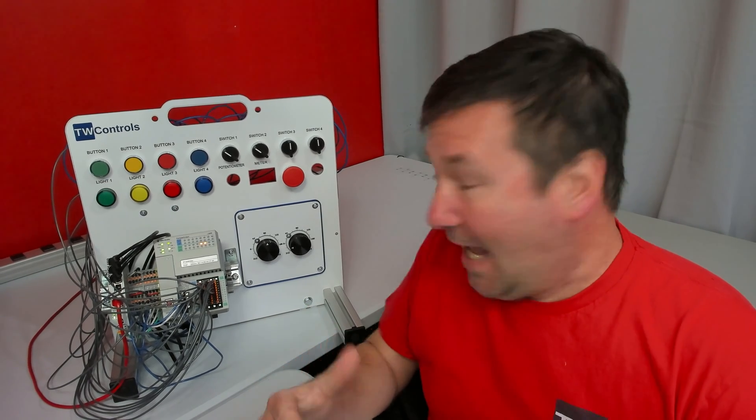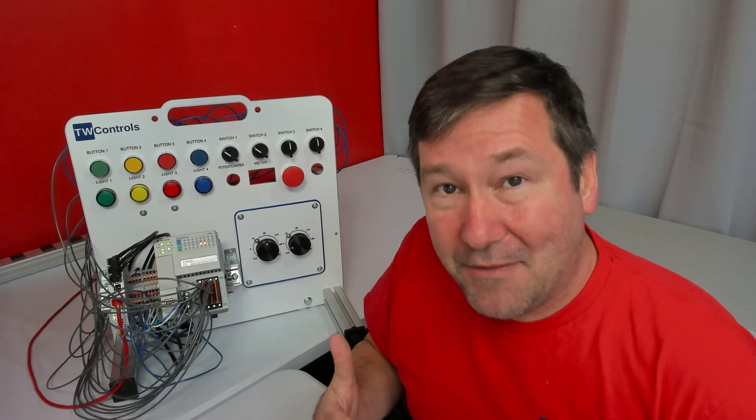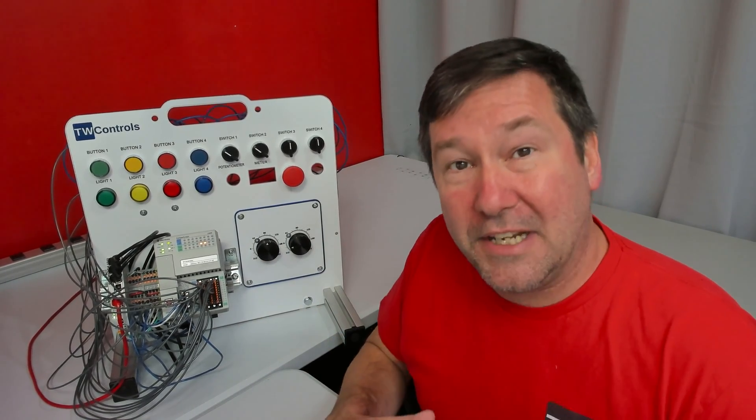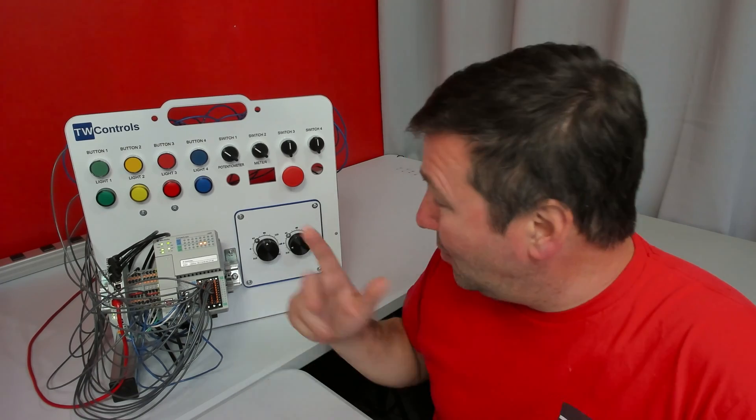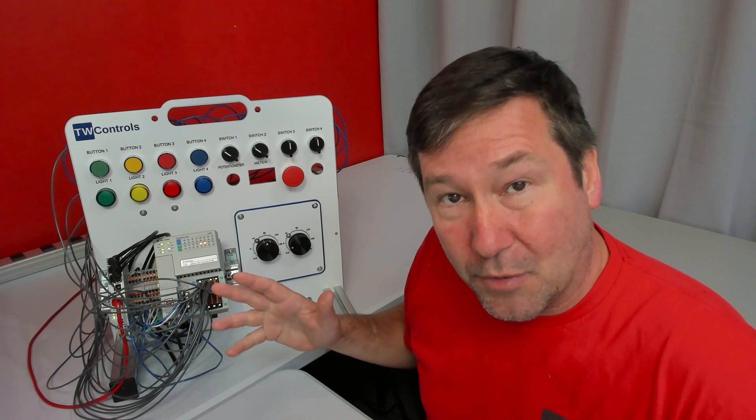In this video, we will actually connect those to outputs on the CompactLogix PLC. Since you have a sinking input, you will need a sourcing output. And coincidentally, the CompactLogix PLC outputs are sourcing.